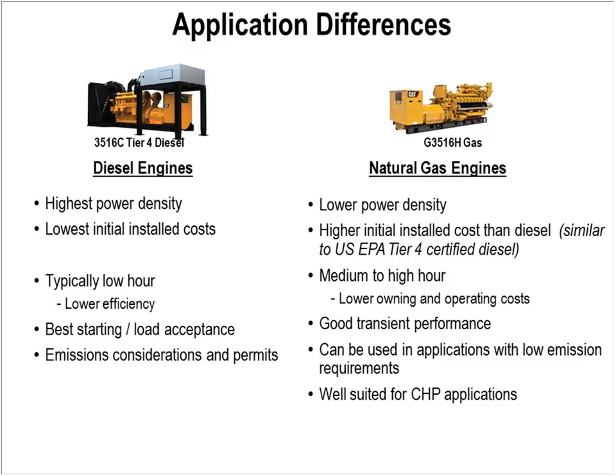And so the gas engines have historically been challenged by that. Initial cost-wise, diesel engines are basically at probably a 20 to 30% lower first cost than natural gas would be. That's in a Tier 2 situation. If I have the total Tier 4 package, including the SCRs on the engine, the gas and diesel engines tend to be about the same cost under those circumstances.